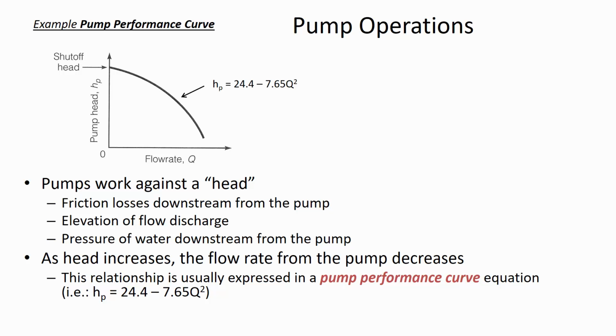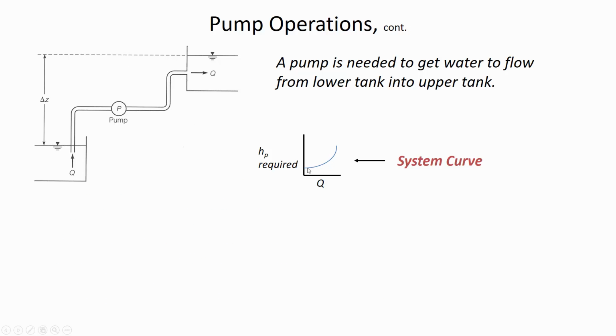When you have a low flow rate, it's adding lots of pump head because the incoming water doesn't have much velocity yet. But the difference between the incoming and the outgoing pressures gets smaller and smaller. It can't add as much pump head. So here's the trend. You tell me, why is the curve shaped this way? Why is it going up for the system curve? Why does it require more pump head, and an exponentially increasing amount of pump head, to increase the flow rate?